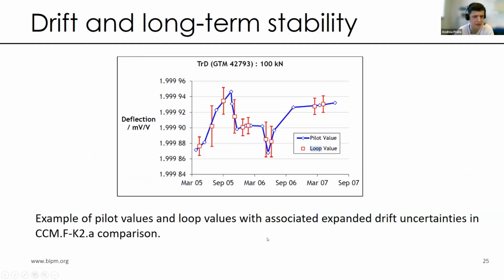We can see an example of pilot values and the loop values with associated expanded uncertainty during CCM.F-K2.a comparison. And we can see the different measurements performed, the different deflections performed in time by pilot measurement, by pilot laboratory, and the loop value evaluated as the mean value, but then, of course, associated with the timing of the participant laboratory, with its uncertainty evaluated according to previous calculations.